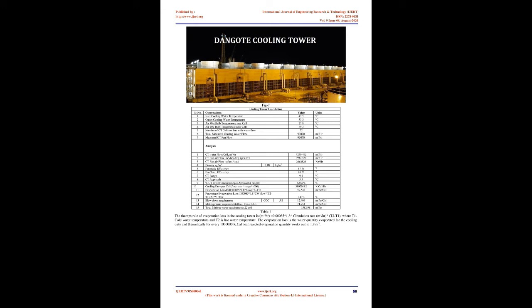Operating conditions. The test was conducted within the following limitations. 1. The wet bulb temperature was measured with a mechanically aspirated psychrometer. The thermometer did not have a least count of more than 0.1 degrees Celsius. The wick was cleaned and continuously supplied with distilled water at a temperature close to the prevailing wet bulb temperature. 2. The average wind velocity was 18 km/h. Wind velocity measurement was made with an anemometer, in an open and unobstructed location within 100 feet of and to windward of the tower.